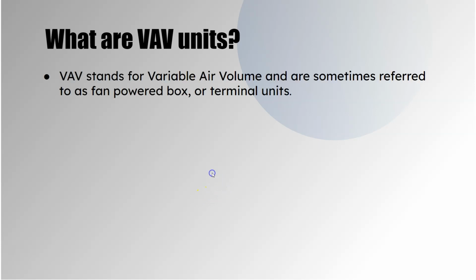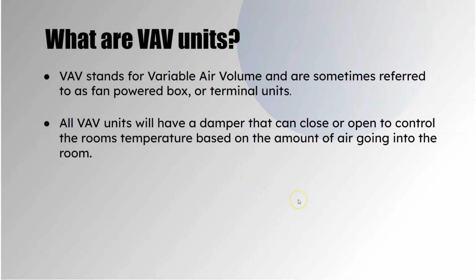So what are VAV units? VAV stands for variable air volume. And sometimes it's called a fan power box, a terminal unit, damper, controls damper. I've heard a lot of different terms for it, and mostly they're interchangeable. So all the VAVs will have a damper that can close or open to control the room's temperature based on air going through the room, right?